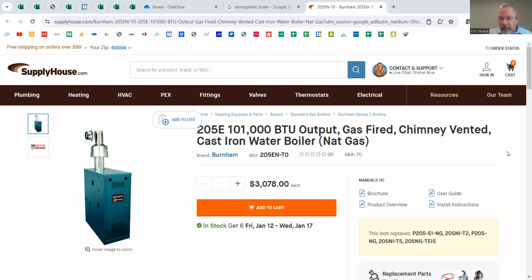So pump zoning is one way to do it. Typically more expensive. Multiple pumps gets more costly. Another one is valve zoning, meaning you can have one pump and then zone valves on the boiler that open and close the water flow to specific areas. And that's where things can get a little complex. But again, it gives you that adaptability and that ability to even things out and make it super comfy.